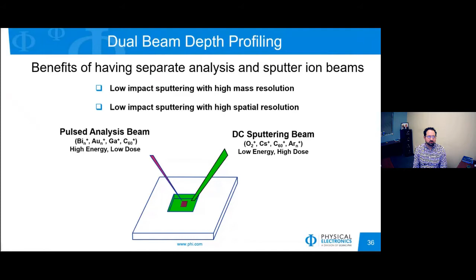And so having high spatial resolution with low energy can be rather challenging. But we can overcome that by using a pulsed analysis beam, a high energy analysis beam, to image with good spatial resolution. How this is accomplished is that the analysis beam hits the sample and turns off, and then a DC beam of low energy, high dose removes material, and that material is thrown away and then turned off, and then the pulsed analysis beam comes back on. This is repeated until you go through your desired depth of interest.